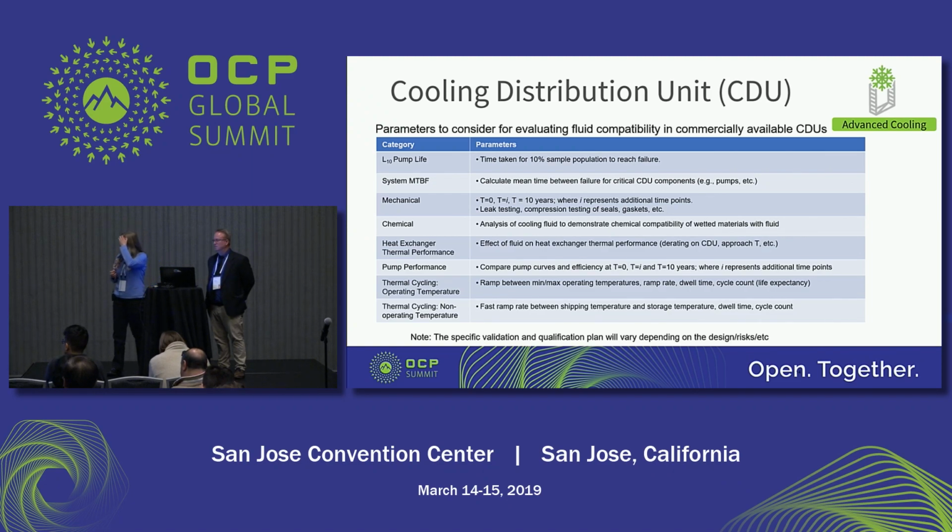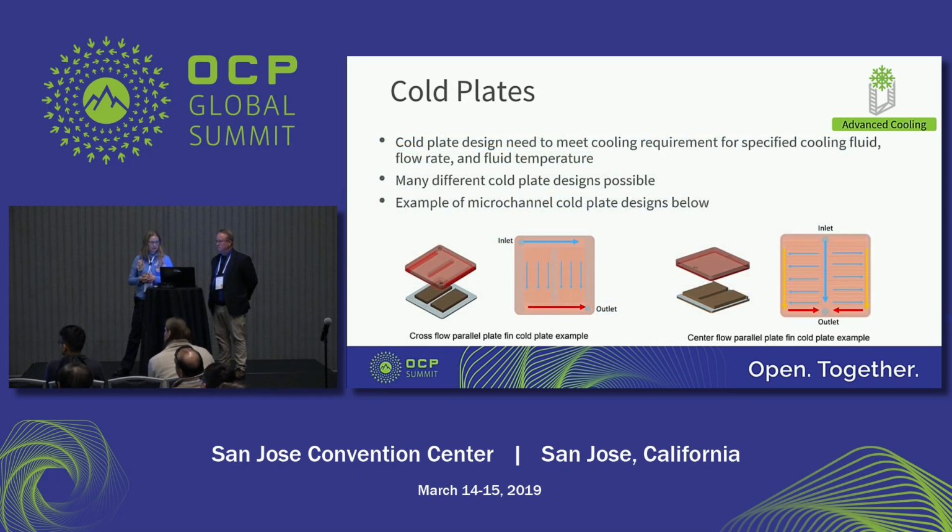But each of this, so it's really of high importance to do an FMEA, right, failure mode effects analysis in order to determine for the particular CDU and fluid that you're using, where are the highest risks? What is it that you should focus on when you do a detailed validation and qualification plan for that? So we've worked with several CDU suppliers in collaboration on this as well.